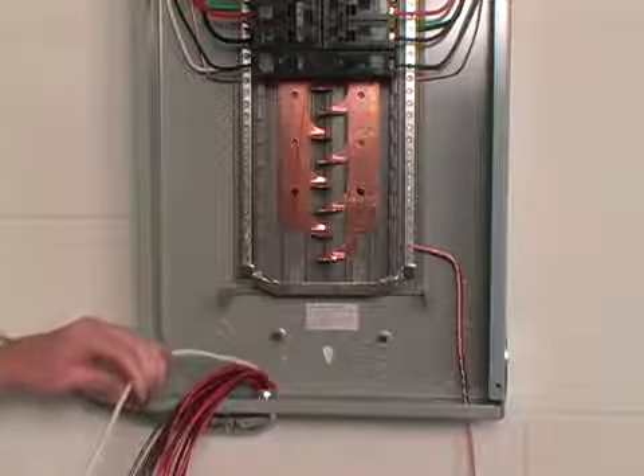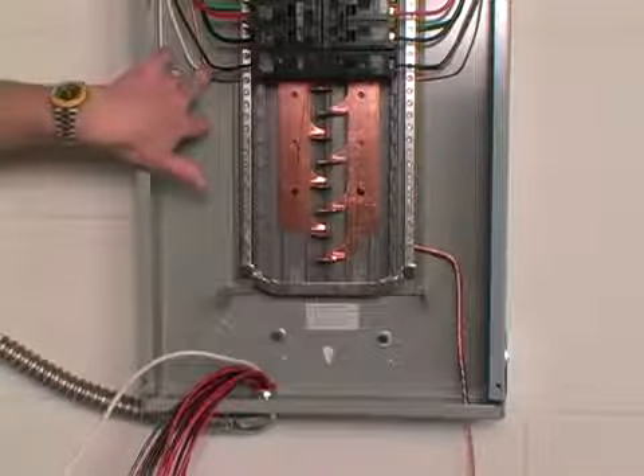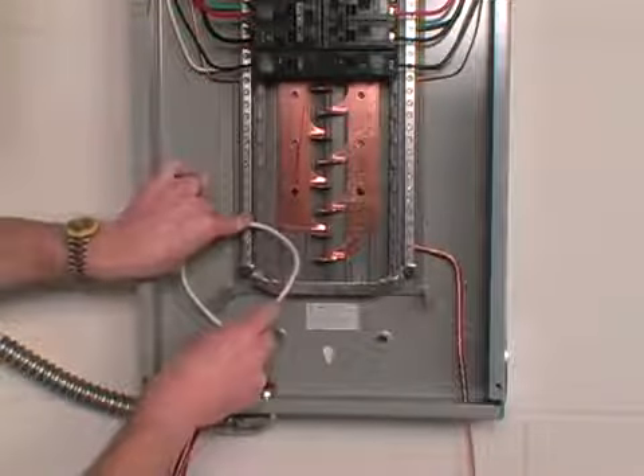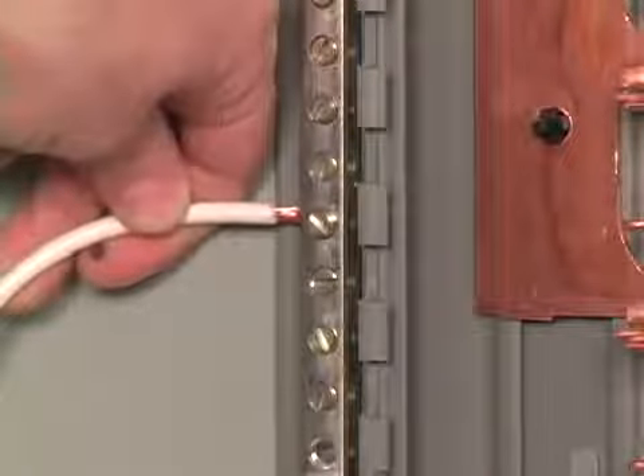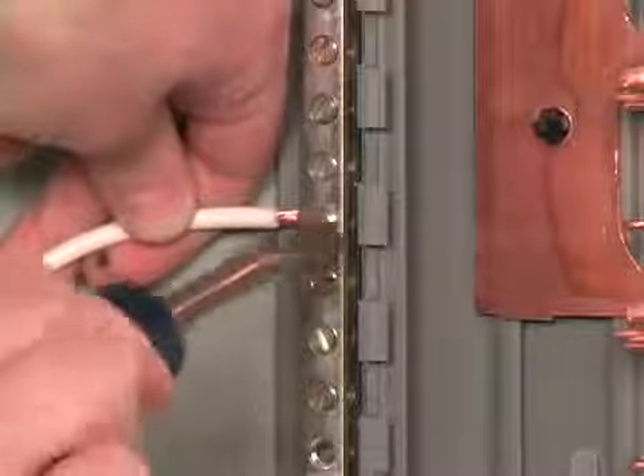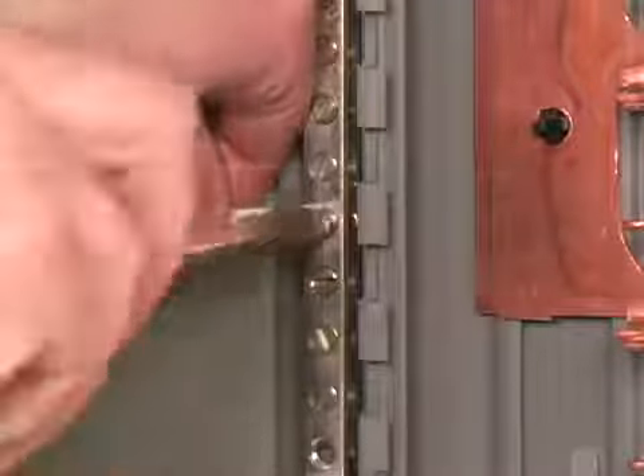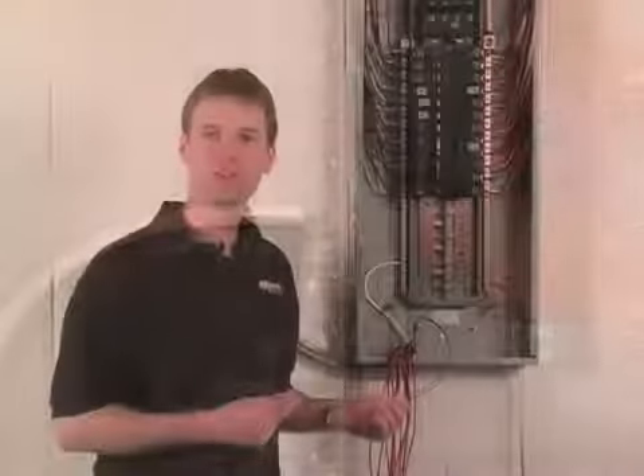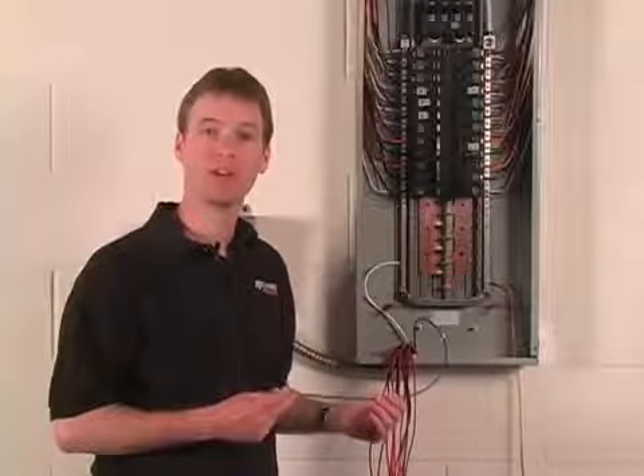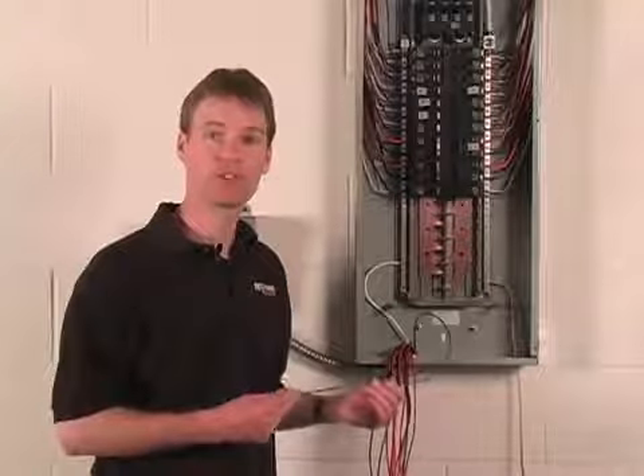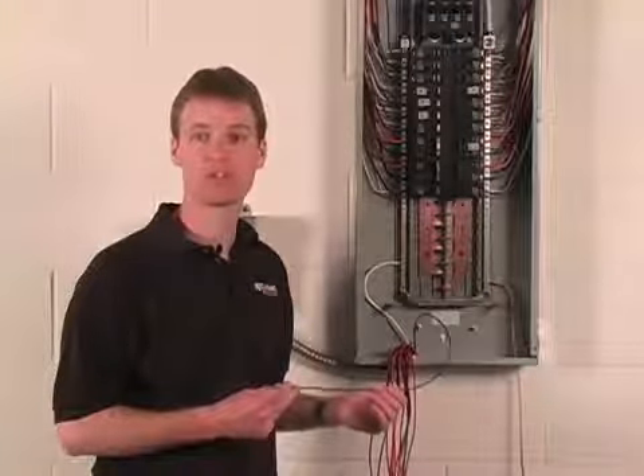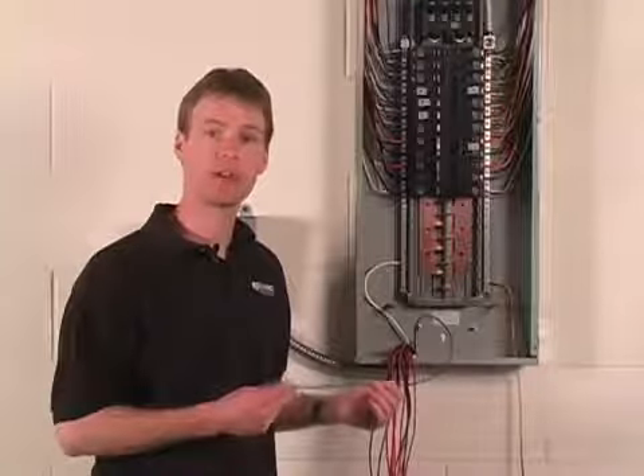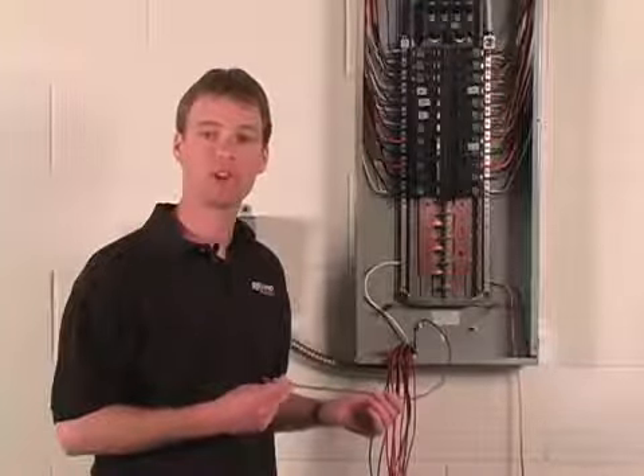In the main panel, locate the neutral bar. This is where all the white wires are attached. We're going to attach the white wire from the transfer switch to that bar. Attach the white wire to any open position in the neutral bar. The green wire should be attached to the grounding bar in the main panel. In most cases, the grounding bar and the neutral bar are the same. The only exception is if you are installing the transfer switch on a sub-panel. In our case, the grounding bar and the neutral bar are the same, so I'm going to attach the green wire in the same bar as the white wire. Make sure you tighten all screws to the panel manufacturer's specifications.